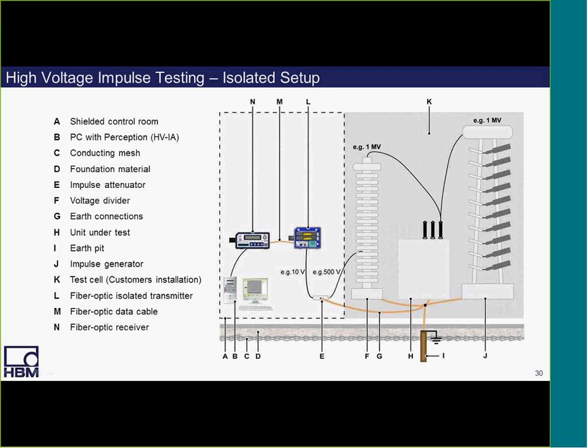Now, here in this example, the 500 volts is at the attenuator input, and then 10 volts is at the output, which is connected to L, the battery-operated high-voltage fiber optic isolated digitizer transmitter, which outputs the fiber signal, M, as in Mary, to the fiber optic receiver, N, as in Nancy, which is connected to B, as in Boy, the PC running the perception software for control and analysis of the impulse test.